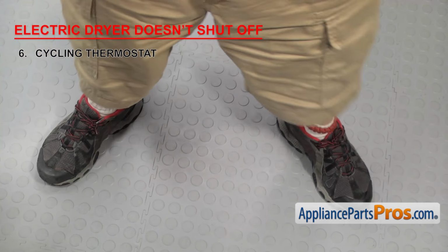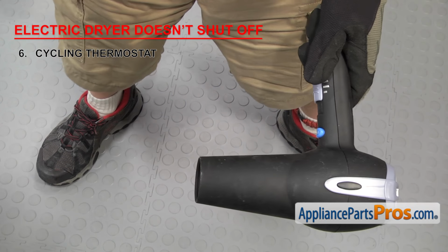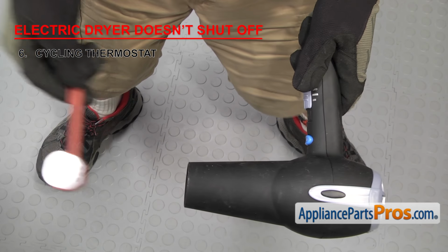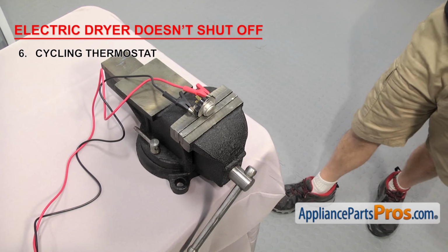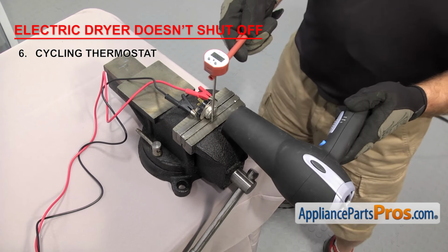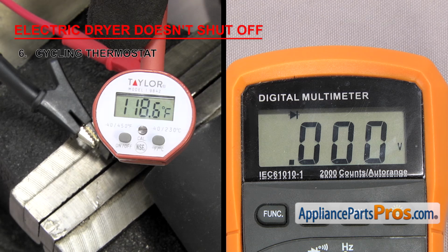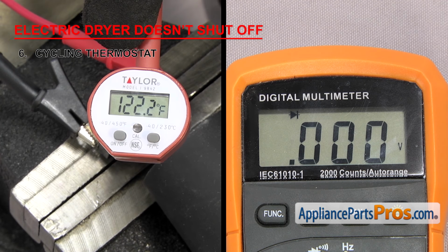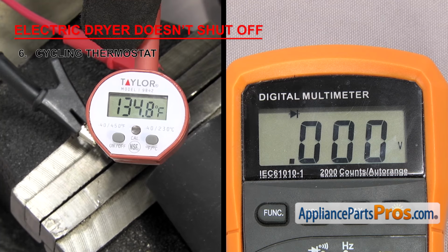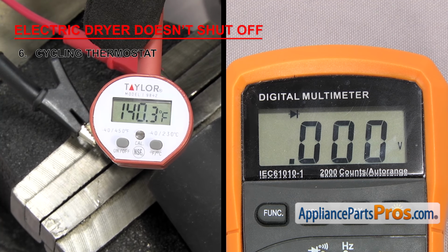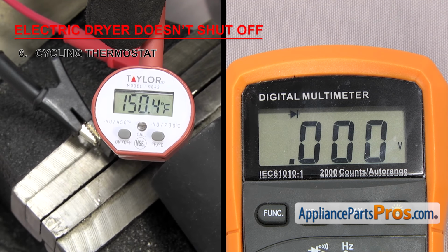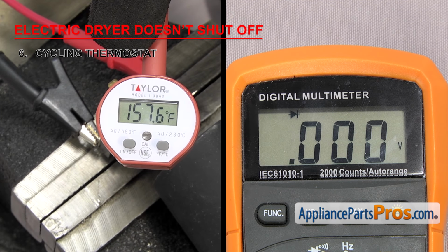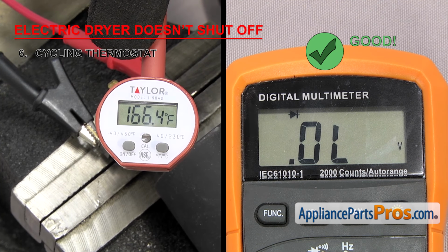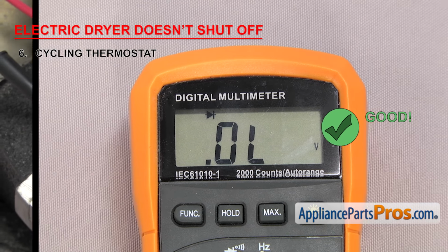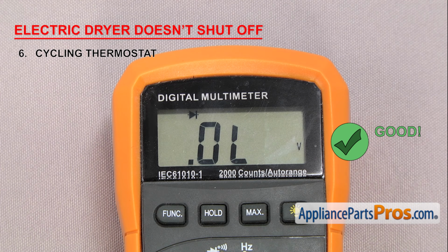You can use anything to heat it up. We're going to use a blow dryer, and as it heats up, we'll read the temperature with a thermometer. As you're heating it up, you want to go slow so that the inside of the thermostat has time to come up to the correct temperature, otherwise you might get a bad reading. You want to make sure that it doesn't break continuity before the rated temperature. Once you get past the rated temperature, check the meter again to make sure that there's no longer continuity. If the thermostat loses continuity before the rated temperature, it'll need to be replaced.